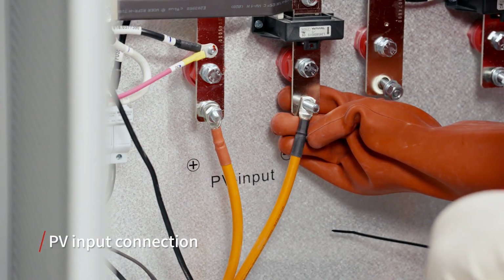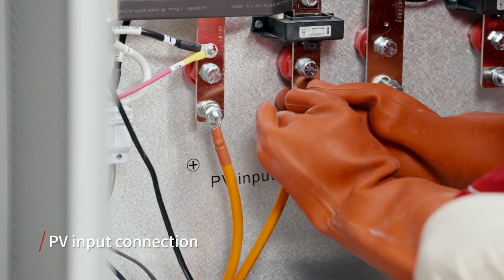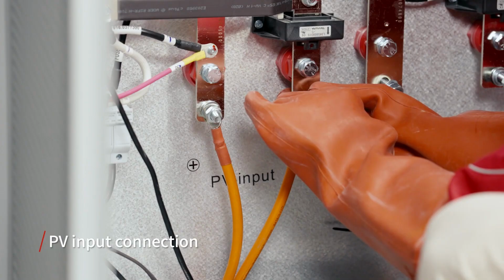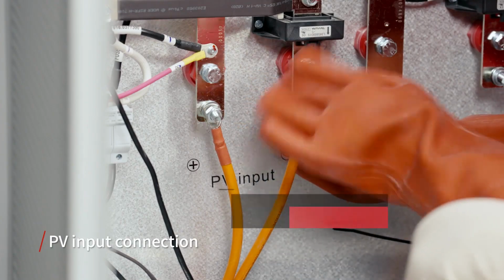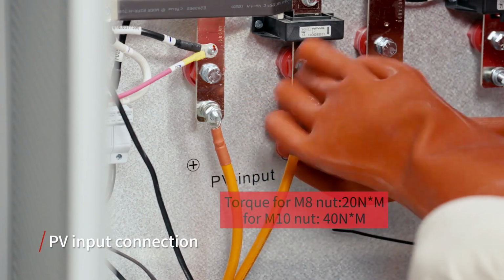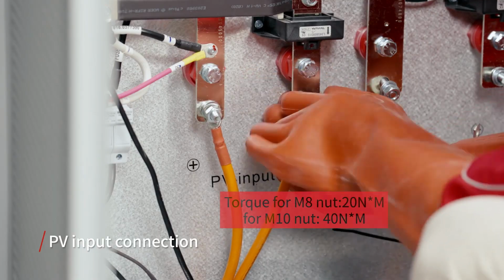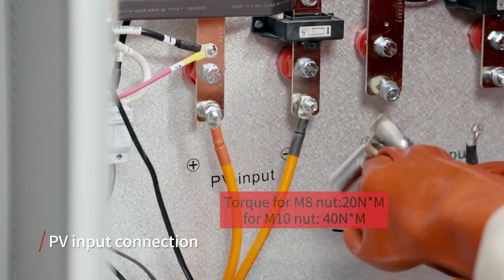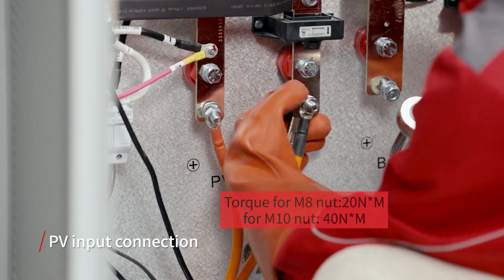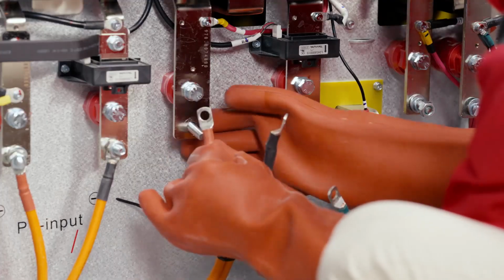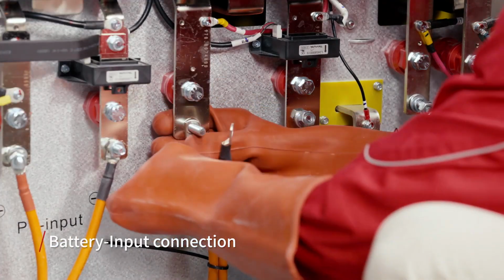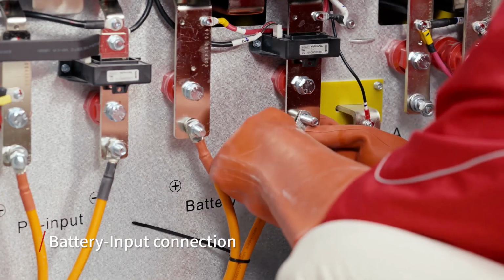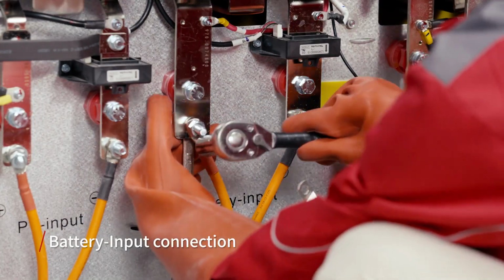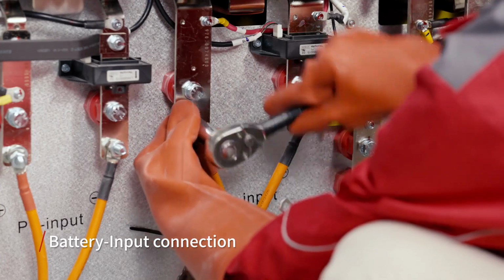Connect PV cables. Notice the positive and negative poles. Measure positive and negative of PV and make sure there is no ground fault on the PV side. Herein and in the following wiring operations, make sure you torque check the nuts after connecting all the cables. Connect cables of the battery cabinet or battery rack to the breaker marked battery input. Measure the positive and negative of the battery side.